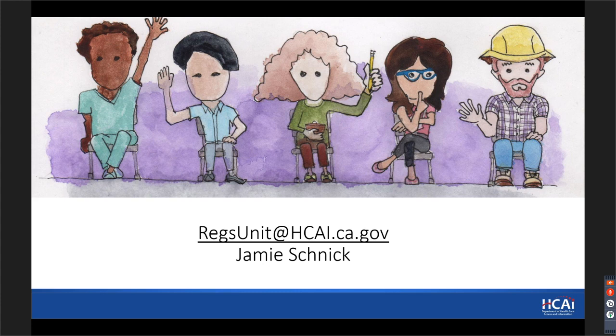This is not a code change, but we understand that there is an HCAI policy change, as there are several hospitals which have equipment branch receptacles rather than normal or optional standby receptacles at the patient bed location. We understand this is no longer approvable and it does not meet the model code. Can you confirm?